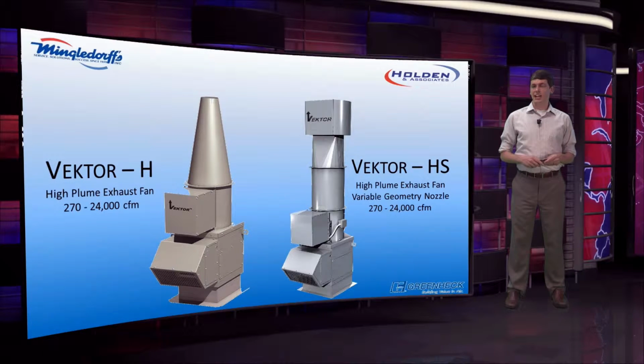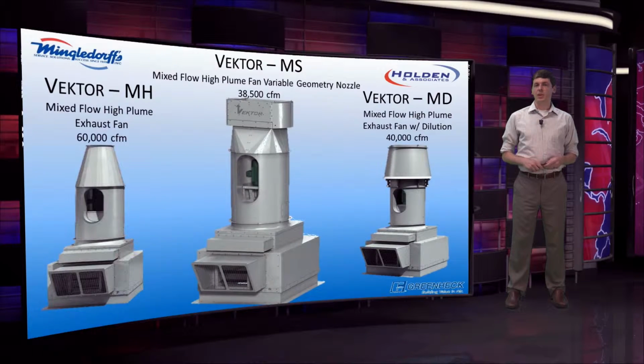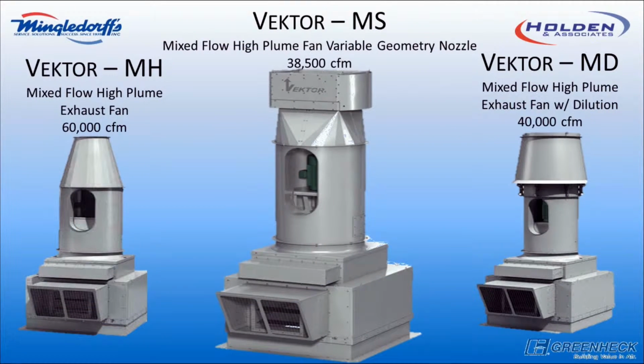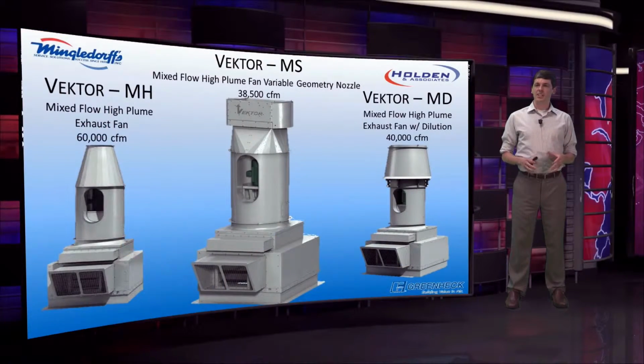You'll also see the Vektor HS, the H fan with the new variable geometry nozzle, which we'll discuss in more detail in a minute. Now we'll talk about the Vektor M series of fans. The Vektor M fans use a mixed flow fan wheel for efficient air movement. You'll see the MH, the MD, and the MS fans on your screen. The Vektor MD allows for dilution up to 300% when the application dictates. The Vektor MH is similar to the Vektor H in that it is just a high plume exhaust with no dilution.